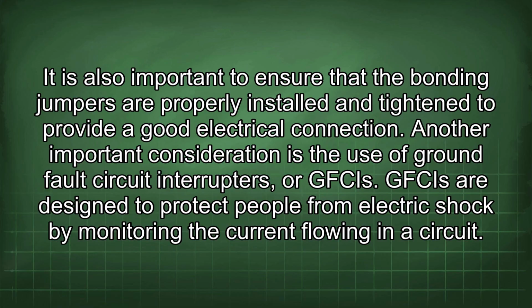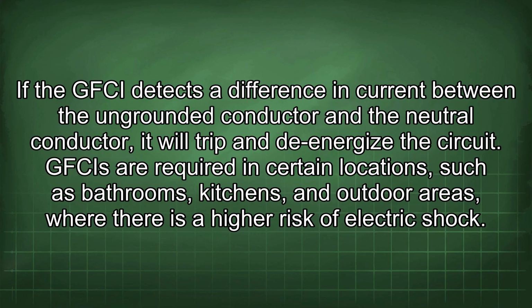Another important consideration is the use of ground fault circuit interrupters, or GFCIs. GFCIs are designed to protect people from electric shock by monitoring the current flowing in a circuit. If the GFCI detects a difference in current between the ungrounded conductor and the neutral conductor, it will trip and de-energize the circuit. GFCIs are required in certain locations, such as bathrooms, kitchens, and outdoor areas, where there is a higher risk of electric shock.